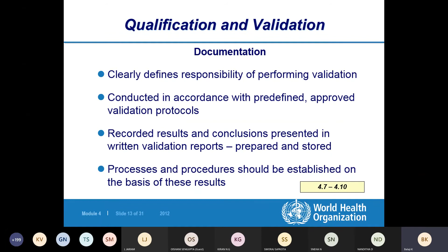Once everything has been completed and the validation is successful, the procedure is revised or updated according to the outcome of the validation result. That is the reason I mentioned the autoclave. If you are using a new parameter like 135°C and the result is successful, you have to update your SOP to include the 135°C sterilization process.